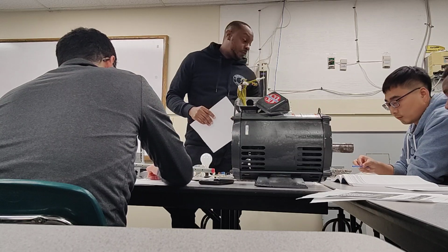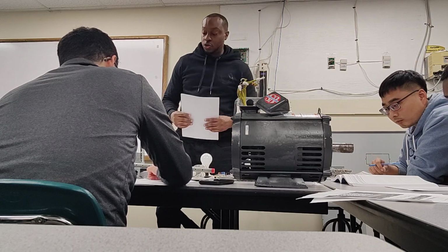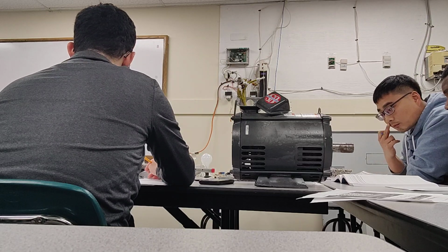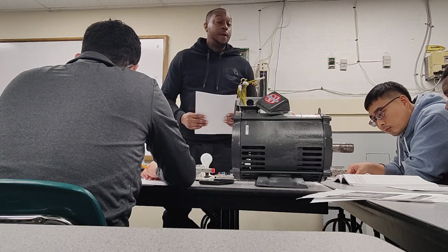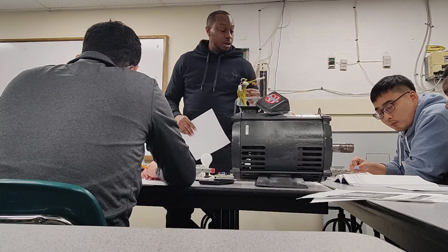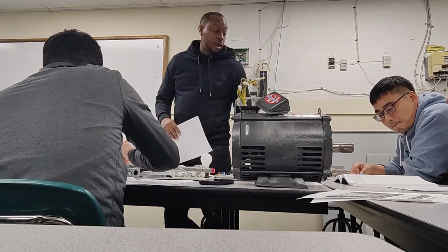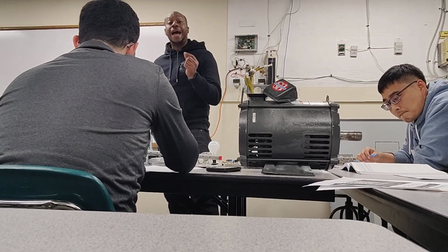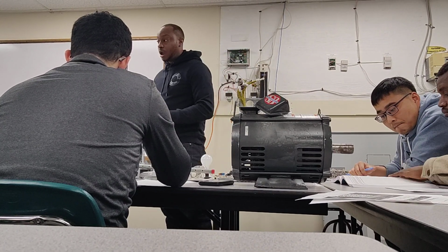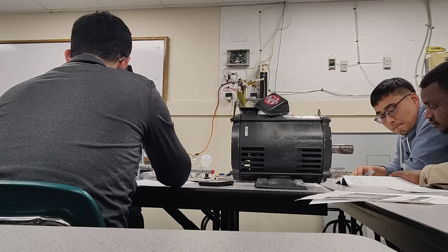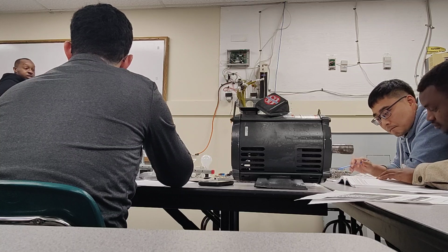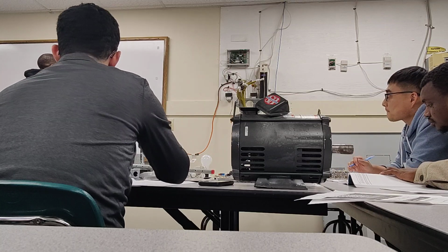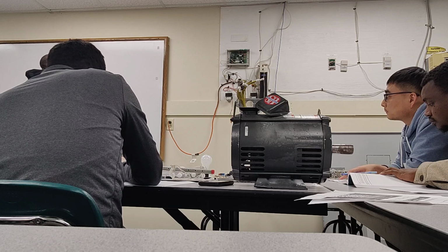All right. What this does is it tells you the dry bulb conditions. Turn to 105. It tells you all the different dry bulb conditions based upon different cities and locations. In those cities and locations, they're pulling the temperature readings from the airport. So if I give you a city, you want to look for the airport, the AP or the IAP. IAP is the International Airport. Two things you're going to use off that table are the 1% dry bulb number and the 99% dry bulb number.